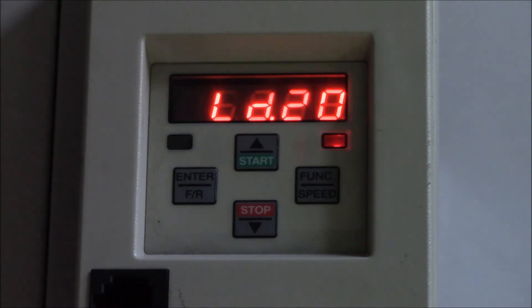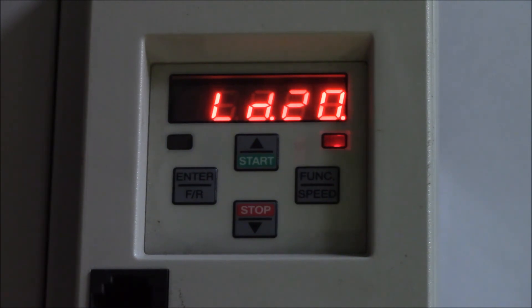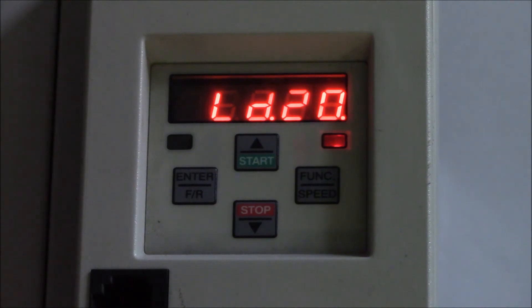If you have a geared motor, you will have to program all of the motor parameter settings starting with LD1 and ending with LD8. Always make sure LD20 is less than 1500.